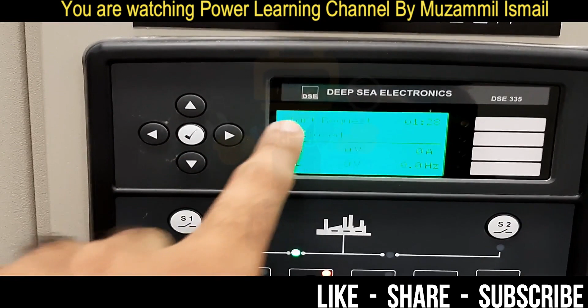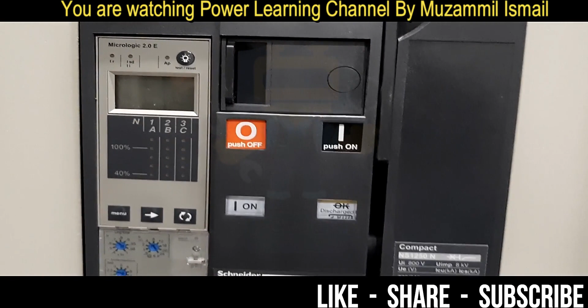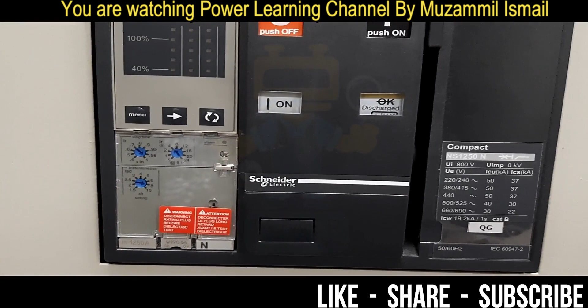Now the normal supply is off, QN is off, and the generator is ramping up - the generator indication is on. You will see it's warming up now. After the warming up timing expires, the breaker will be closed. As you see, S2 is available now, the QG breaker is on, and the QN breaker is off.